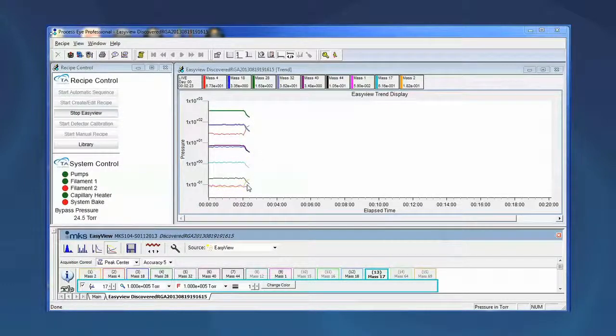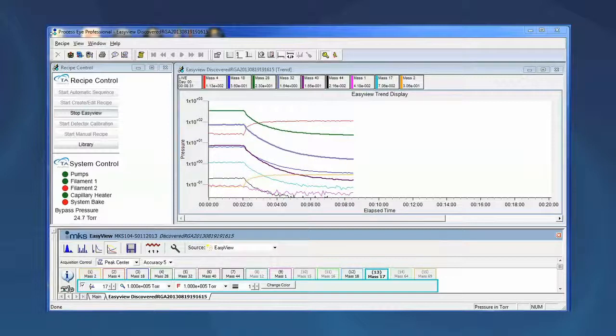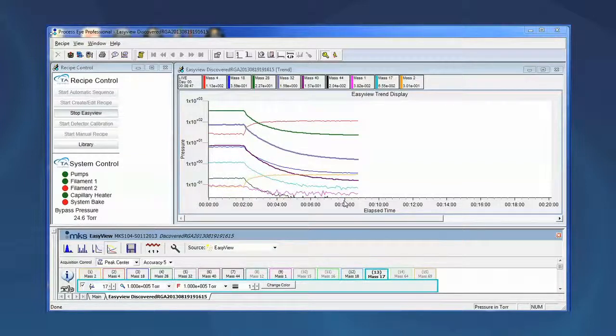After a minute or so, the downward trend of the atmospheric gases continues as the helium increases. Note that the water, hydroxyl, and hydrogen ions all follow the same trend with the other atmospheric gases. Our chamber gases come into equilibrium and we are almost ready to start our experiment. After a few more minutes, we see that our atmospheric gases have essentially hit a minimum. Notice that we closed the furnace at roughly the 2-minute mark and arrived at the minimum at approximately 8 minutes. If you are running samples that may be sensitive to the atmospheric gases or humidity, you may want to consider a 10-minute isothermal at the beginning of your TGA experiment to ensure complete gas exchange.